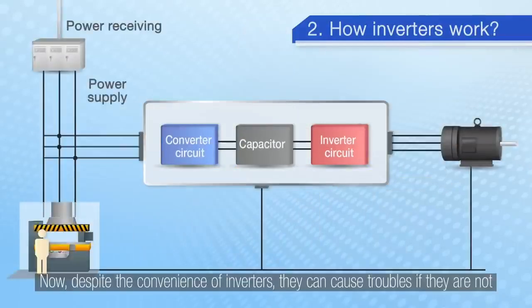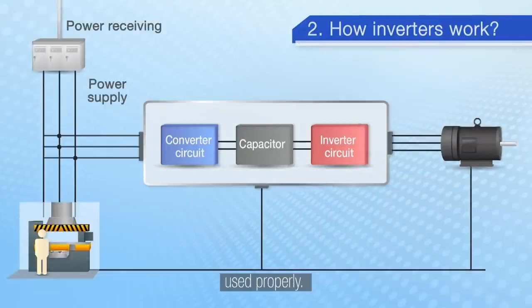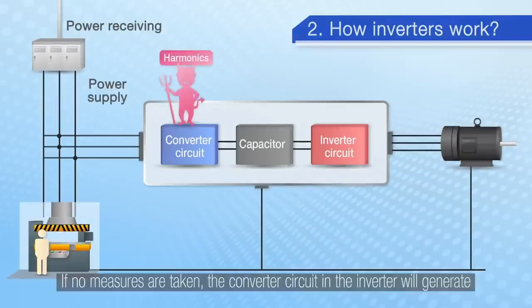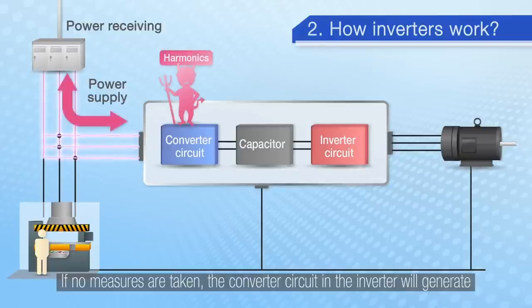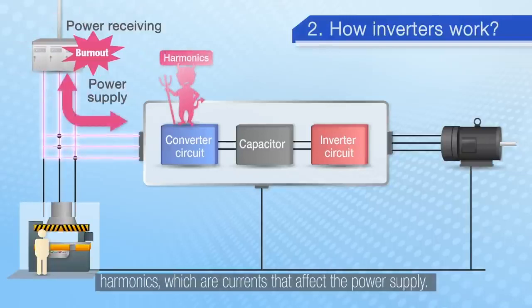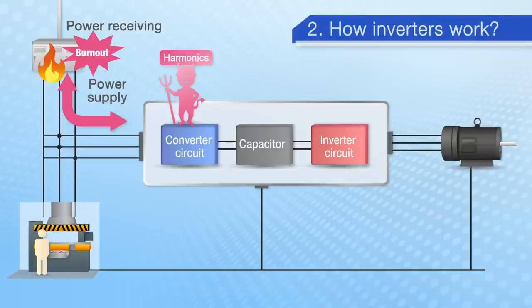Now, despite the convenience of inverters, they can cause trouble if they are not used properly. If no measures are taken, the converter circuit in the inverter will generate harmonics, which are currents that affect the power supply.